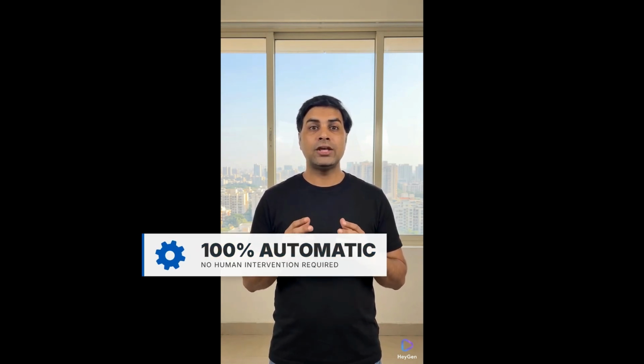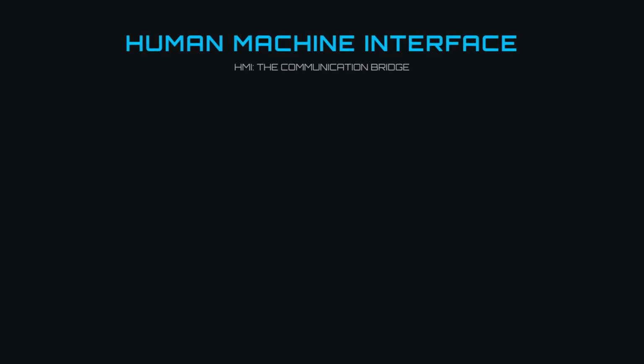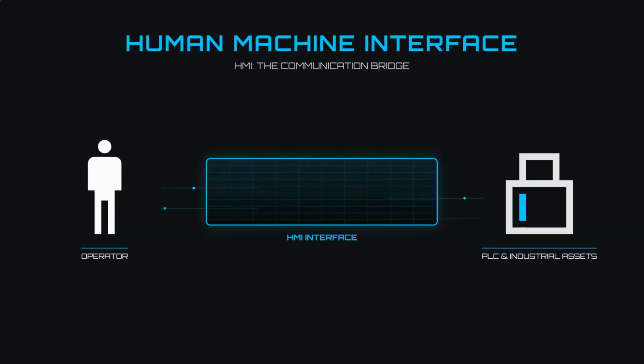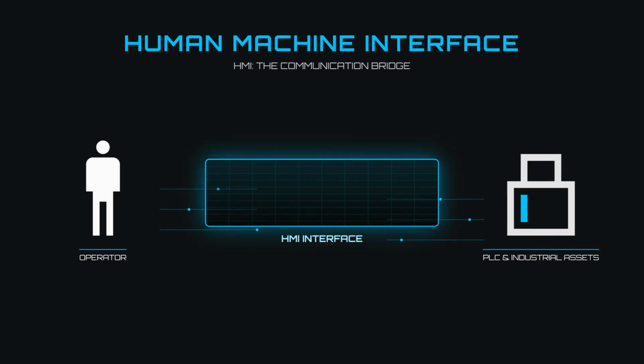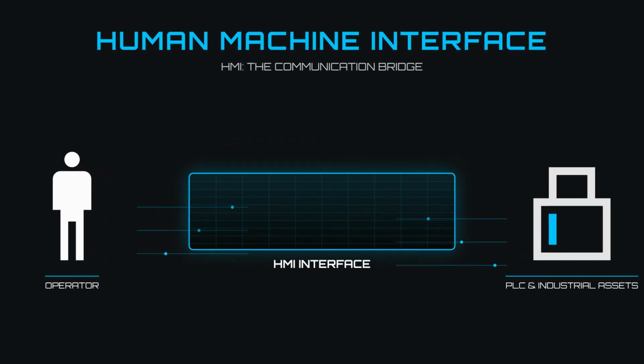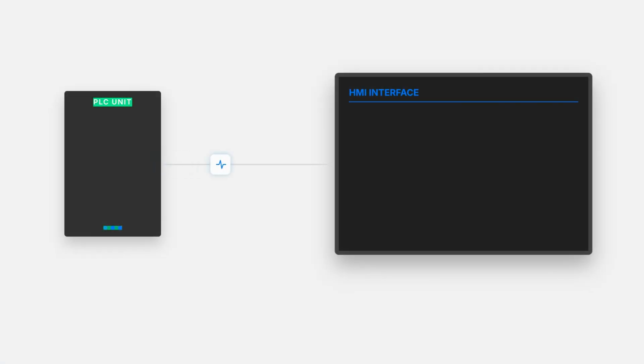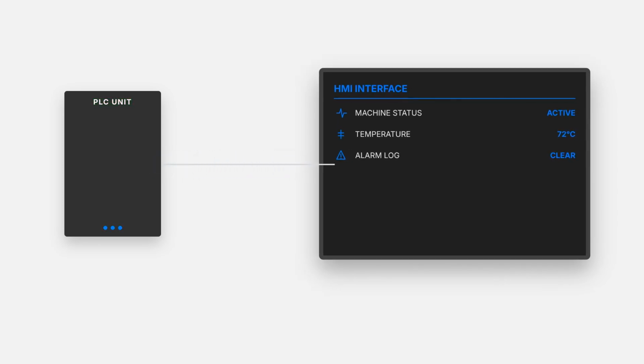Now let's talk about HMIs. HMI stands for Human Machine Interface. You can think of an HMI as the communication bridge between humans and machines. The PLC and HMI continuously exchange information. The PLC sends machine status, temperatures, alarms, and production data to the HMI. The HMI displays this information to the operator. At the same time, operators can send commands back to the PLC using the HMI. For example, they can press start, stop, reset alarms, or change machine settings. This two-way communication makes operation easy and efficient.